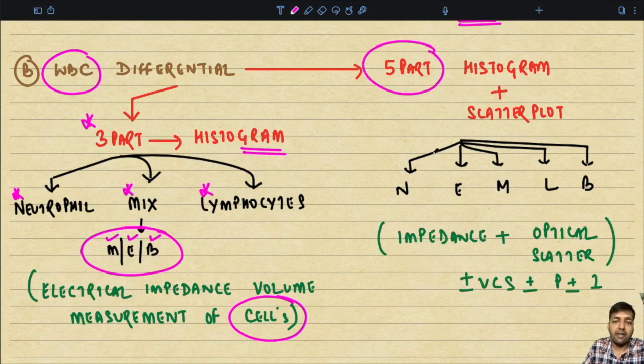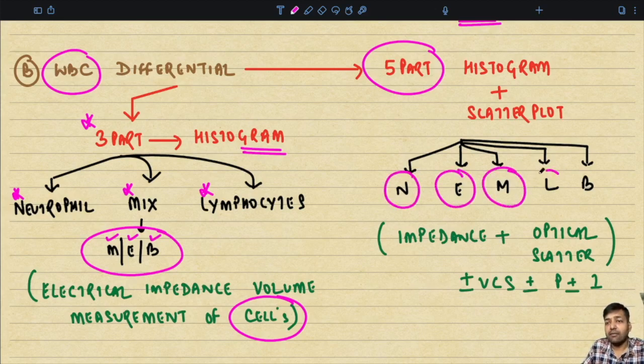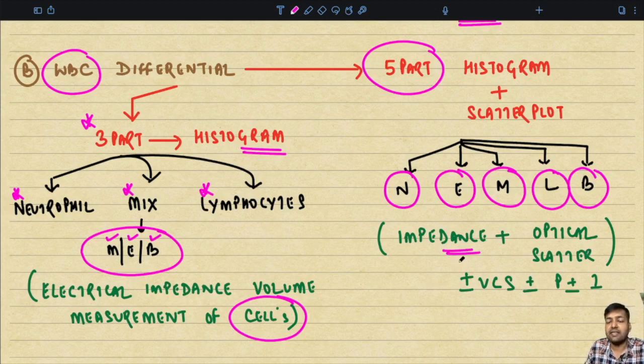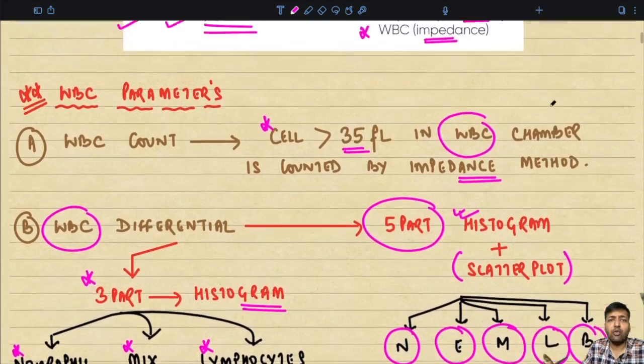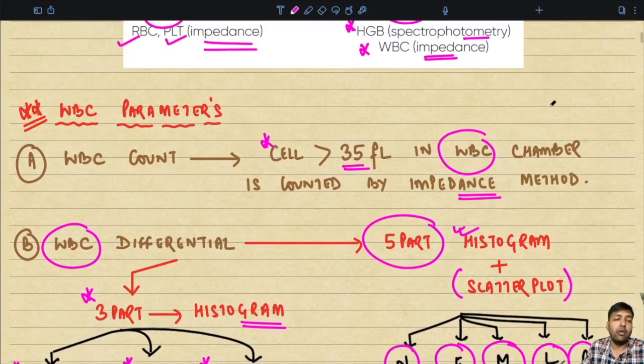The five-part automated hematology analyzers differentiate between individual white blood cells — neutrophils, eosinophils, monocytes, lymphocytes, and basophils — separately. They are based on the principle of impedance as well as optical scatter. Some machines may also use VCS technology, peroxidase staining, or immunological methods. The five-part machines not only create histograms but also create scatter plots or scatterograms, which we will discuss later.